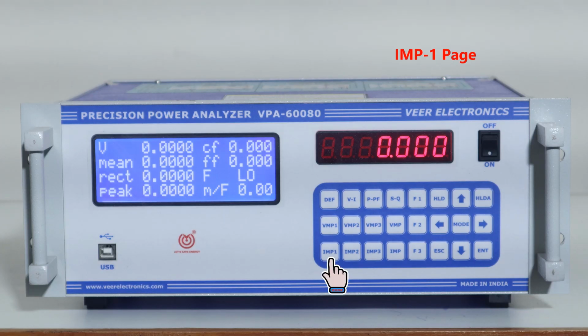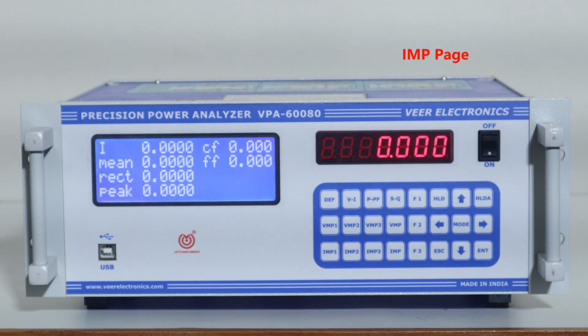This is IMP1 page. It shows RMS, mean, rectified and peak value of R phase current. Also shows crest factor and form factor. Same parameters applicable for IMP2 page and IMP3 page. IMP page also shows RMS, mean, rectified and peak value of average current. Also shows crest factor and form factor for average current.